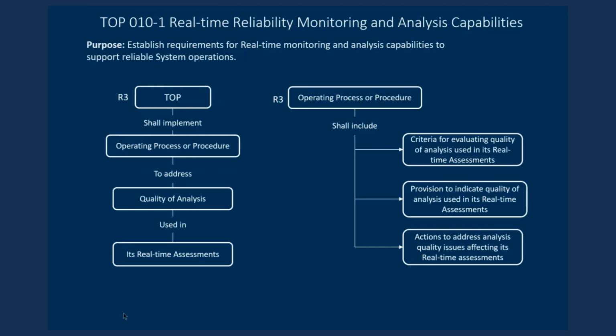These new applications are relatively recent. They were motivated by the blackout in the Southwest in 2011, that every transmission operator had to run contingency analysis at least once every 30 minutes. You can have a modeling error, or you can have some bad data that will actually make those programs give results that are not realistic at all. We're giving you the analysis tools to make your own decisions about, is that a real violation or is it potentially due to bad data, without having to call in the operating engineer.